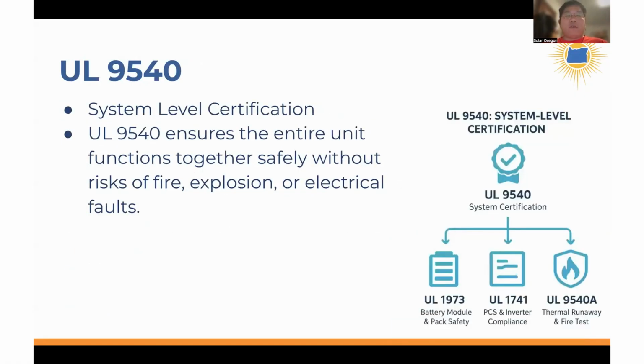And then UL 9540 is a system level certificate - to get this certificate, you basically have to have a list of all the combinations tested. So for example, with a battery and an inverter being separate components, each combination has to be tested and certified. Therefore, if you buy batteries and inverters from different brands, it's unlikely you're going to get a UL 9540 certification. Whereas if you buy the battery and inverter from the same brand, there's a good chance you can find a combination that has been UL 9540 certified. To what extent is this really required?